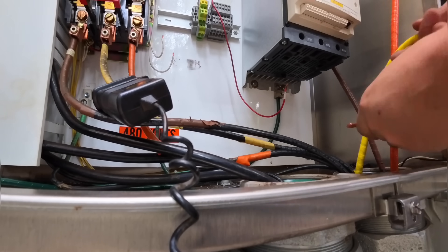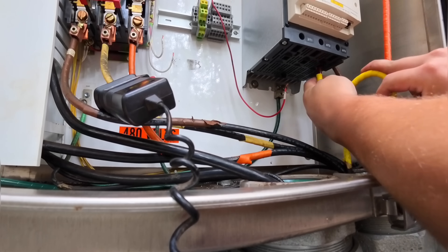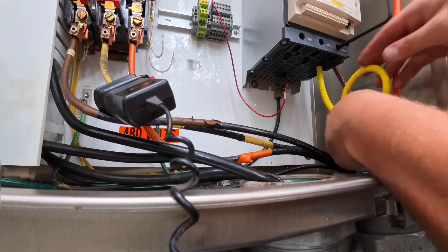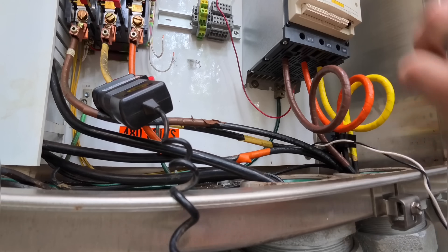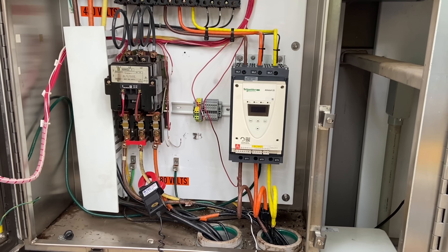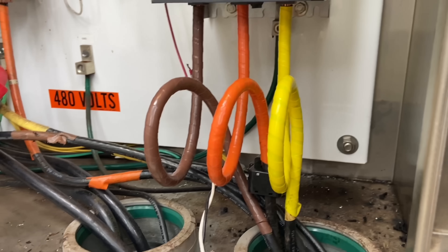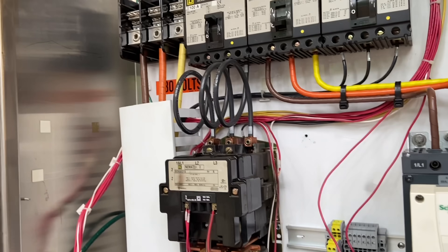Let's move on to the load side. I'm going to start off with my grounding like you do, especially since it's behind all the other wires. I didn't have my crimper with me, so I didn't use a big ring terminal — I just attached a mechanical lug to the grounding stud, which is fine for this installation. And then we go ahead and hook up our brown, orange, and yellow. I did put little service loops on these because the PMs done at these stations require taking current readings, so it is nice to have that spot to attach your meter to. I moved it to the load side because I wanted to. And of course, we got a fresh coat of tape on that too.